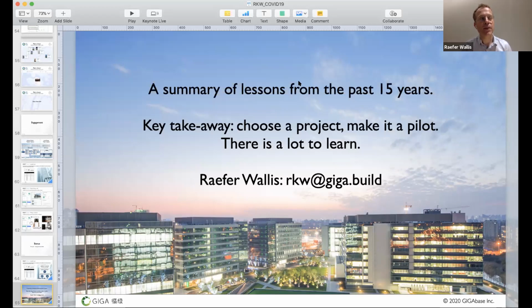I need to be careful because I could go on for hours about this, but typical other things we've found—because we tend to work with tall buildings—the difference in particulate matter, temperature, and humidity between the 22nd floor or the 56th floor is radically different from what's going on at the ground floor. But the average mechanical engineer will specify the same filter top to bottom, which is obviously unnecessary.